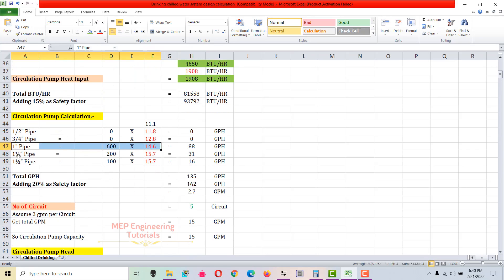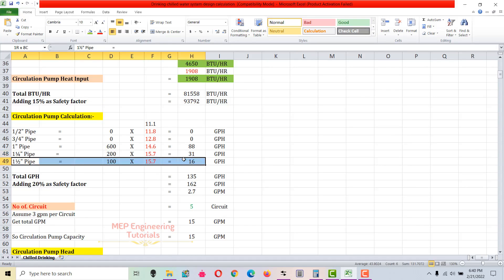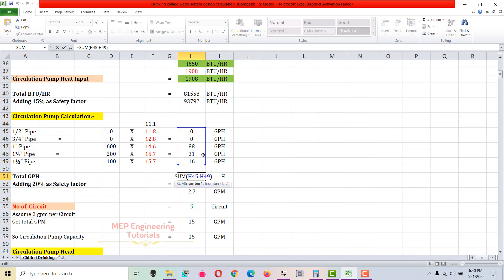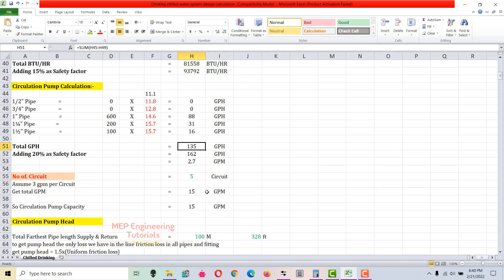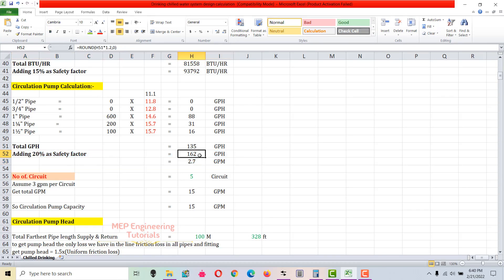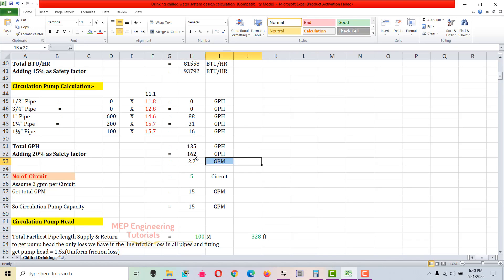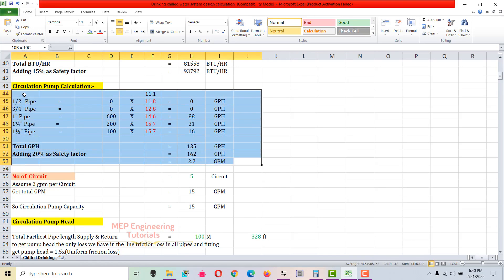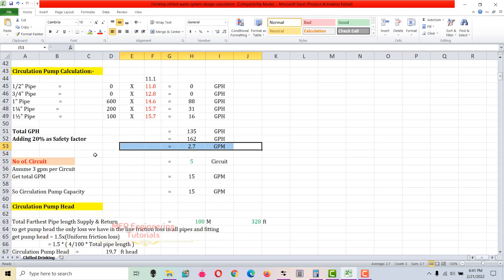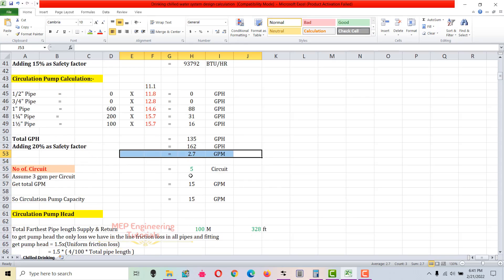Do the same for 1-1/4 inch and 1-1/2 inch pipes, and sum all to get the total — 135 gallons per hour. Adding a 20% safety factor gives 162 gallons per hour. Dividing by 60 converts this to 2.7 GPM. However, this doesn't necessarily mean we'll use 2.7 GPM for the circulation pump — we need to check one more criterion.